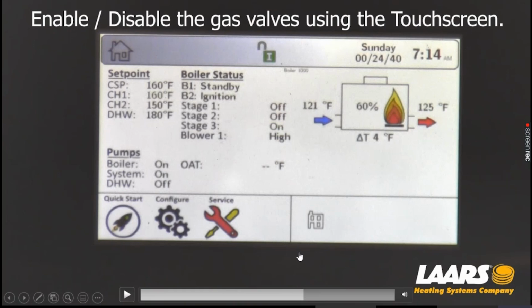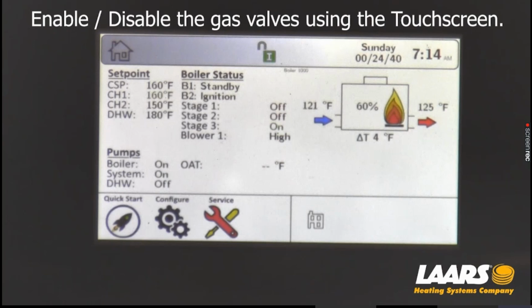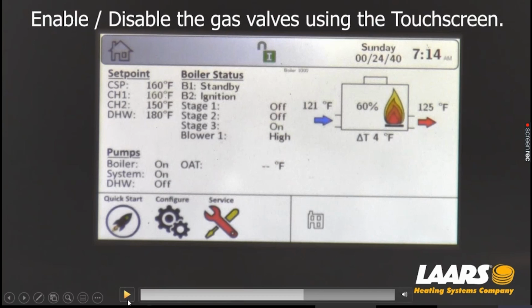You don't have to go in and shut these gas valves off. You can leave it running at full fire. The only time you may have to is, like I said, if your system loop or if you've got a volume water heating application and your tank temperature is coming up pretty quick, you want to be able to give the boiler a nice run time so you can do a combustion analysis. I'll continue to play the video.